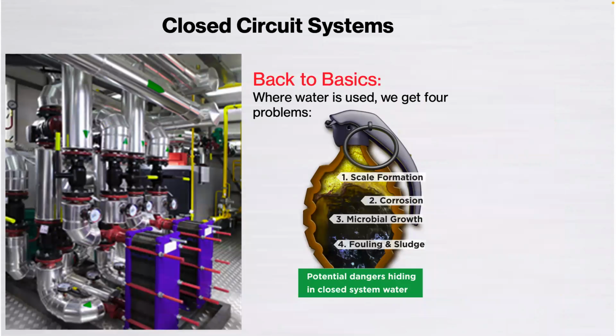So, back to basics, there are 4 main areas that we focus and hone in on with regards to water quality and problems. The first is scale. If we're in a hard water area, fresh water brings in scale minerals, and obviously under temperature they will bake on and cause problems, and not just in terms of adhering to the pipework. They will also break off, and you have these very small particles that are very abrasive, flying around the system and eventually blocking up small orifices. And they also prevent corrosion inhibitors from working effectively. We then get corrosion, with different types of metals within the system. So you can have different types of corrosion taking place, which I'm going to get to shortly.